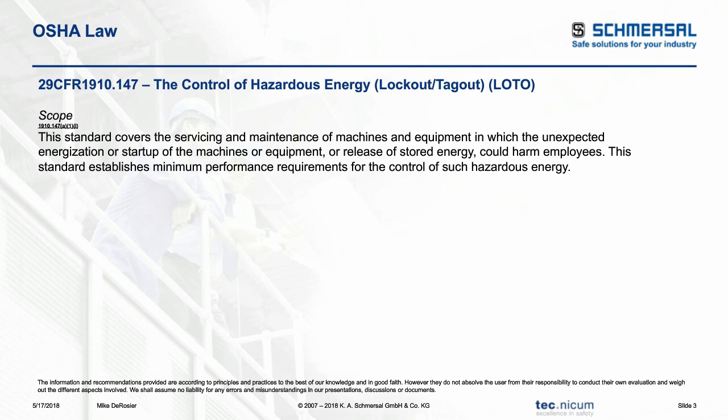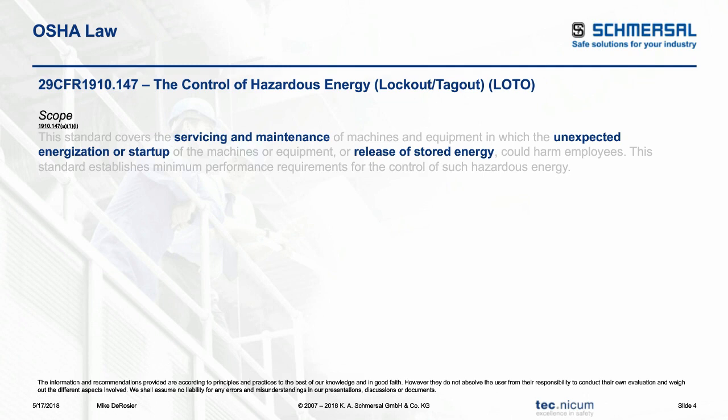So when we look at the scope of the Control of Hazardous Energy by OSHA guidelines, I'm going to highlight a few points. What is Lockout Tagout really supposed to do? The key points in that scope are that servicing and maintenance of the equipment require Lockout Tagout. It has to prevent the unexpected startup or power up related to the equipment, and the Lockout Tagout procedure needs to accommodate the ability to release stored energy. They're the keys to the scope when it comes to Lockout Tagout and the proper materials, components, processes, and procedures as a result.